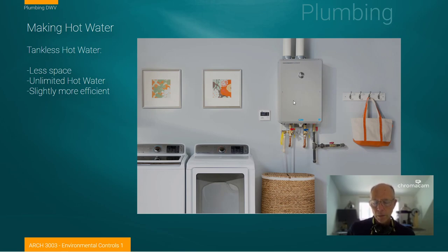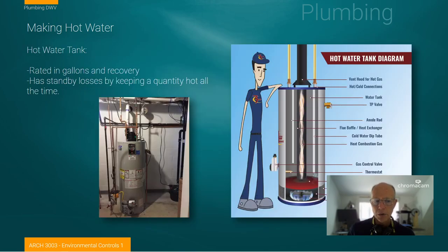They burn intermittently. They burn only as much as they need to heat the water in usually what's considered an instantaneous way. So there's no what is called standby losses. With hot water tanks, the whole tank of water is always at temperature and it's always losing heat to the environment. And so we do provide insulation around them, but we still lose that heat sometimes to where we don't want it.